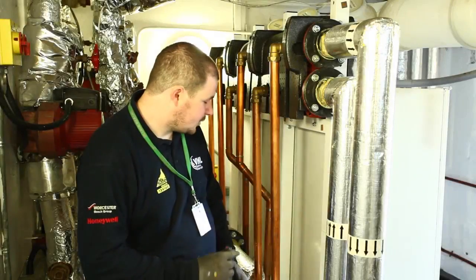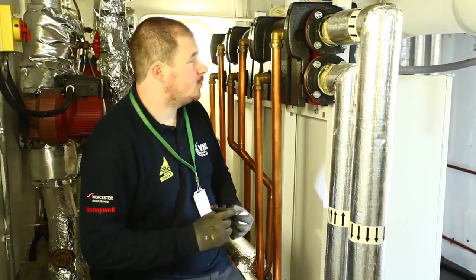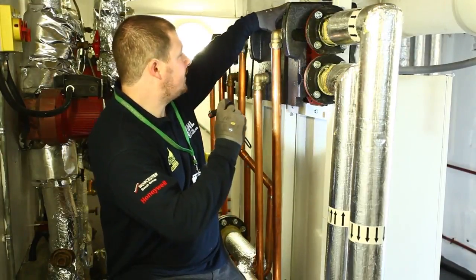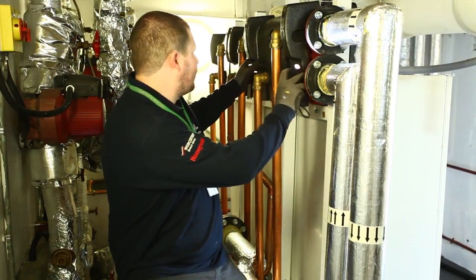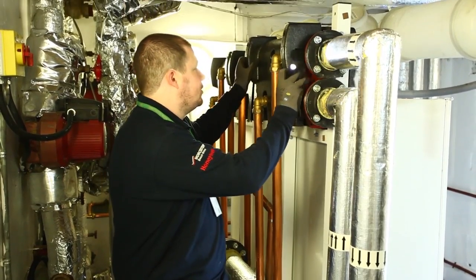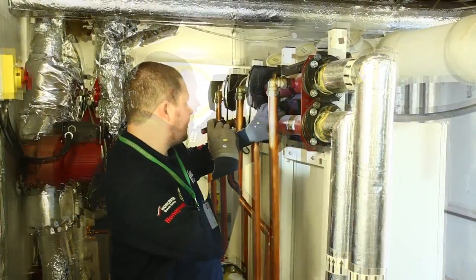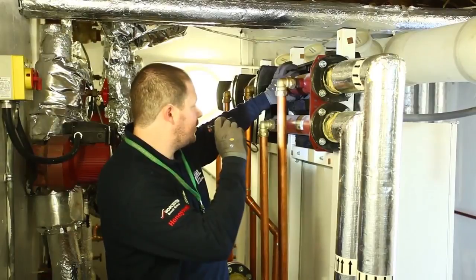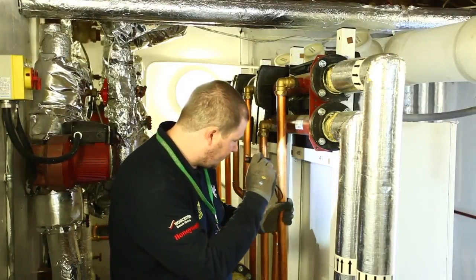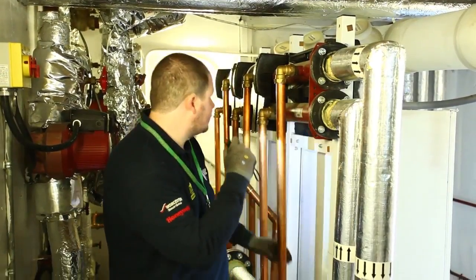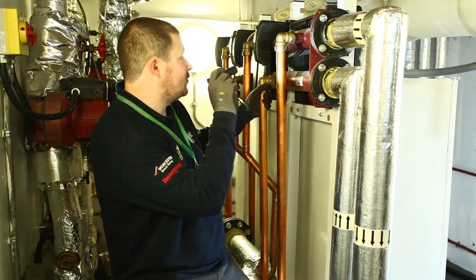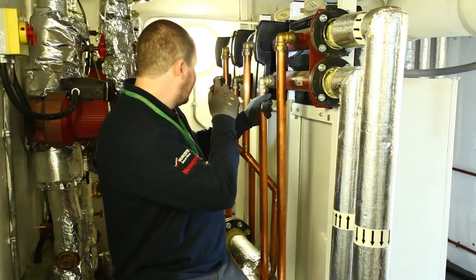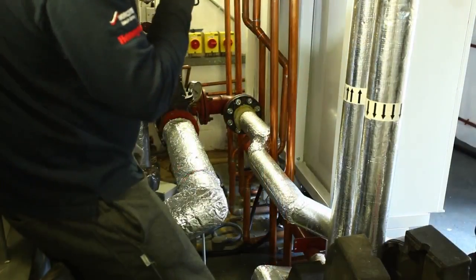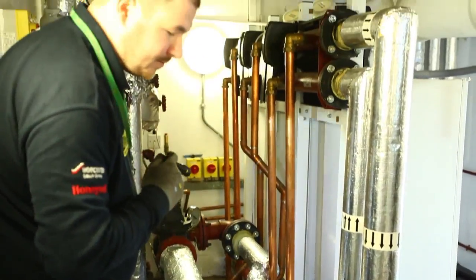So basically, because this one was quite a tricky installation, what we've had to do here is mount the flow return header for the boilers on the back of the boilers. These are our communal flow returns for each boiler. This is what we designed to make sure the boilers work and they are compliant with the manufacturer's instructions, which okayed the installation. And that concludes our installation of this plant room.